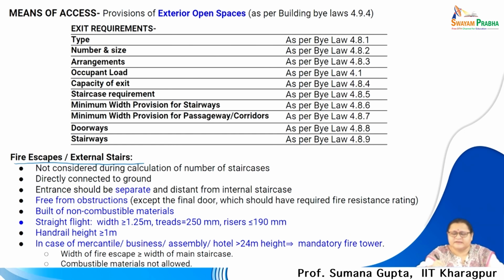Now, these are detailed out in the NBC 4.9.4, and you can get the relevant bylaws for different occupancy loads. As I told, the building may be used for office, residence, or commerce. Based on that, the size and number of staircases are mandated, because the staircase is the only way to connect from the top to the bottom of a building and help in evacuating people, other than the fire lift or the fire tower, which is mandated beyond 24 meters.